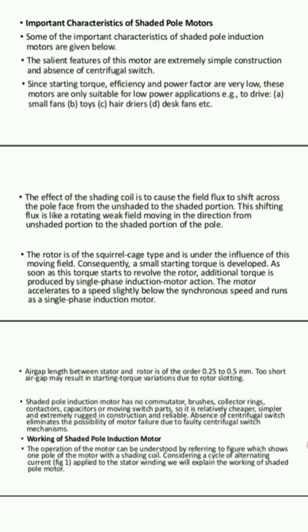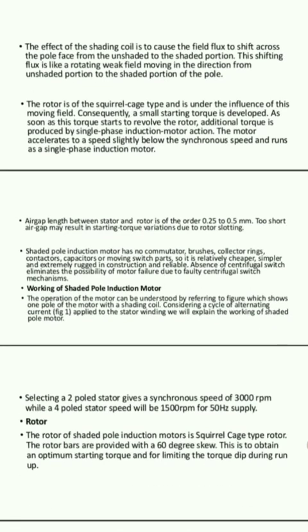As soon as the torque starts to revolve the rotor, additional torque is produced by single phase induction motor action. The motor accelerates to a speed slightly below the synchronous speed and runs as a single phase induction motor. The air gap length between the stator and rotor is of the order of 0.25 to 0.5 mm. Too short an air gap may cause the starting torque to vary due to rotor slotting.